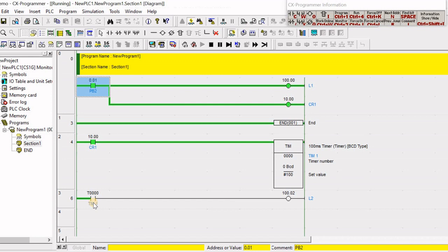But in Omron PLC especially, you cannot do that with an END instruction, so you need another type of override instruction. The END instruction is the simplest kind of debugging opportunity. You can execute up to whatever rung the END is, and as long as there is an END instruction there, you can omit the rest of the program.